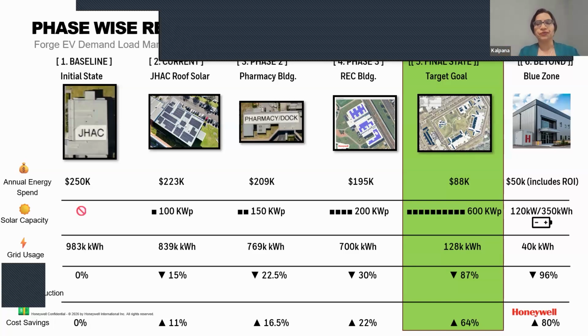So this is what it looks like at the end of the story, where a phase-wise approach is another deliberate option to consider, because each time you design it, there are criteria to think about: how far are the solar panels placed from the inverter, do I need to run AC cables right up to the substation, or can I reduce my cabling? There's a fair bit of detailed engineering that has to be done upfront to get this right every time, especially when doing it in phases.